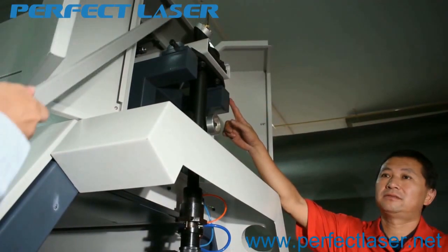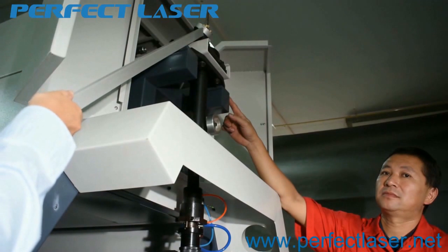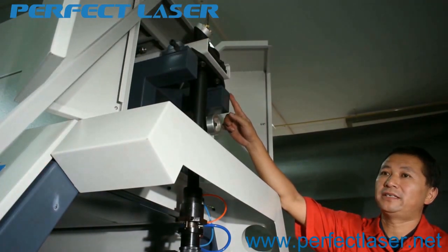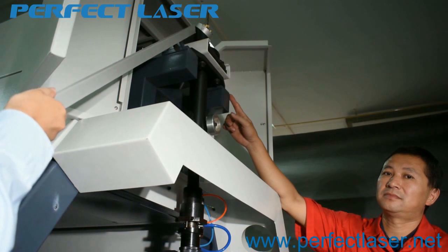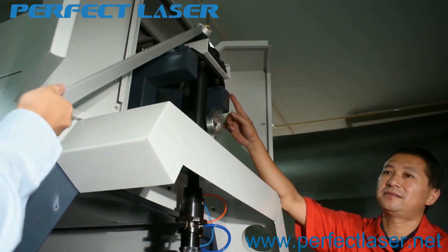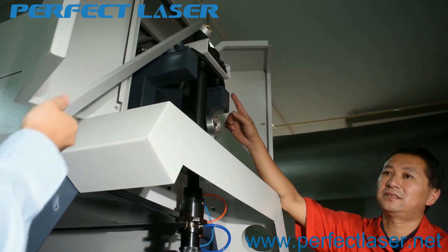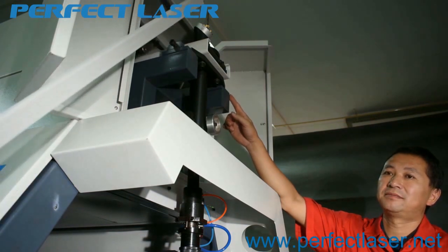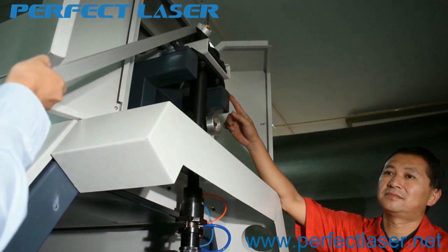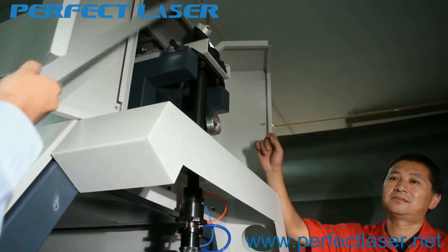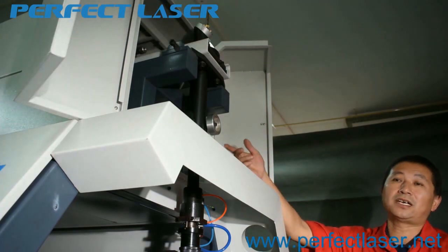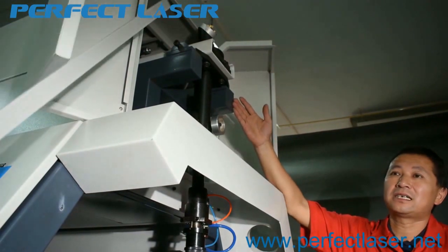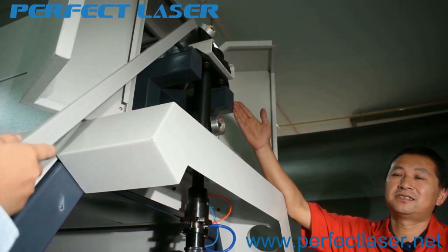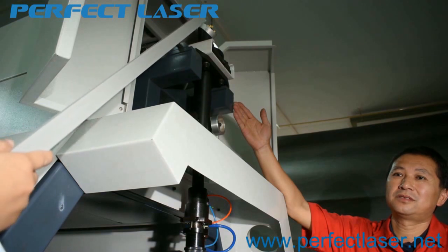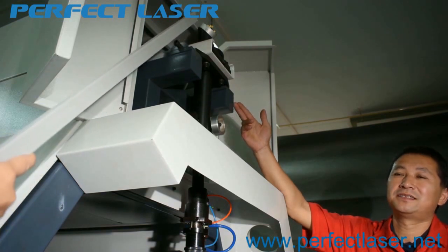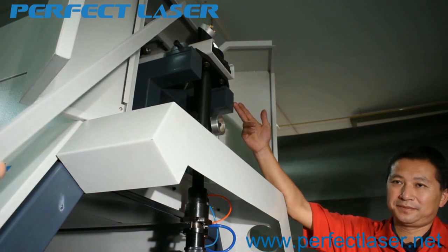Inside of this part, there is a reflect mirror. It is not easy to get broken. Normally, we suggest you check it after 1 year of usage. After 1 year of use, you need to take this reflect mirror out of this part to check. You should check if it has dust on it or if it is worn off. If it is worn off or has dust, you need to change it.